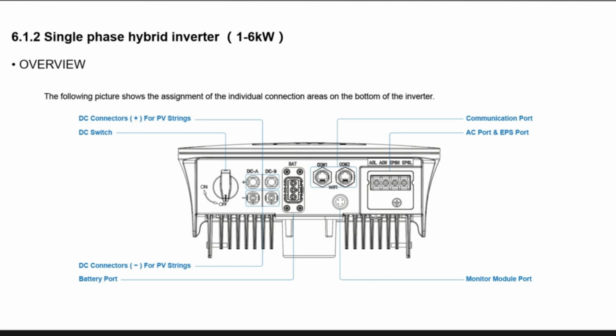With our batteries, you will use an RS485 lead out of the bottom. No, that's the wrong battery. An RS485 lead out of this battery that goes onto the inverter com input. Out of the inverter com input, chop the end of the RS485 lead off and wire it into 4 and 5. Blue goes in number 4, white goes in number 5.